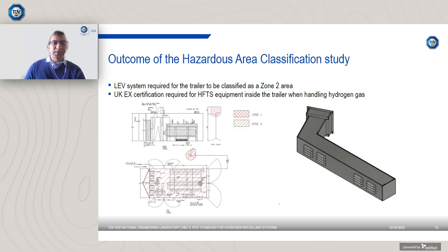Now, this slide shows some of the outcomes from the hazardous area classification study. And what we found is that in order for the test standard, which is going to be transported inside a trailer, to be classified as an ATEX Zone 2 area, we needed to have an LEV fan. Otherwise, what you found is that the zone becomes a Zone 1 area, which makes it very difficult to source suitable measuring equipment. The exit of the vent stack, however, will be a Zone 1 area, and therefore it's got to be a safe distance away from the rest of the test rig.